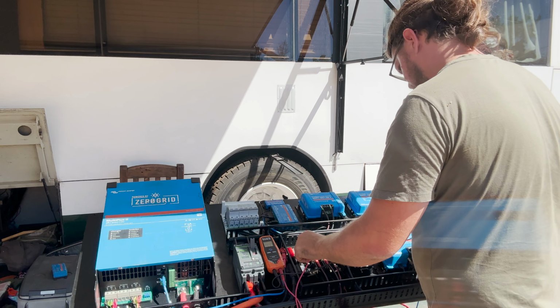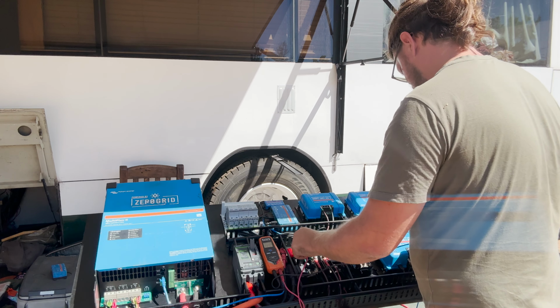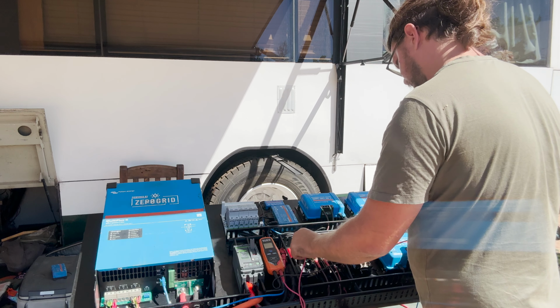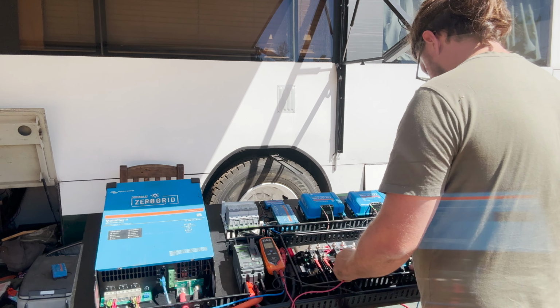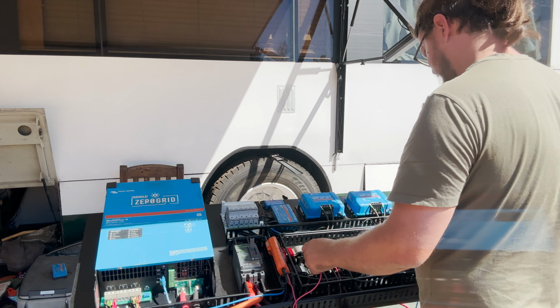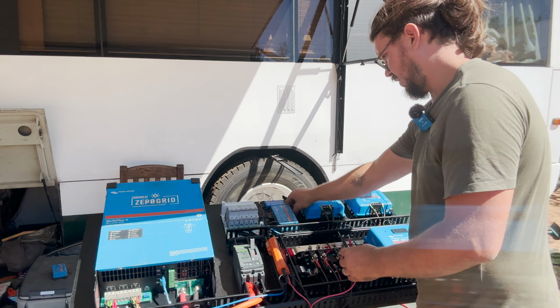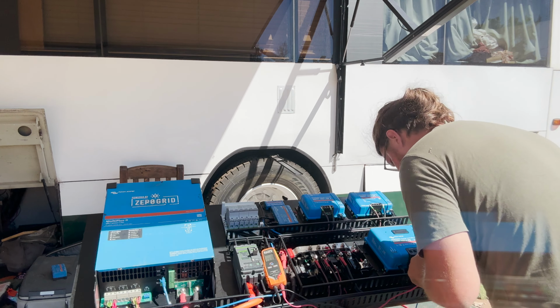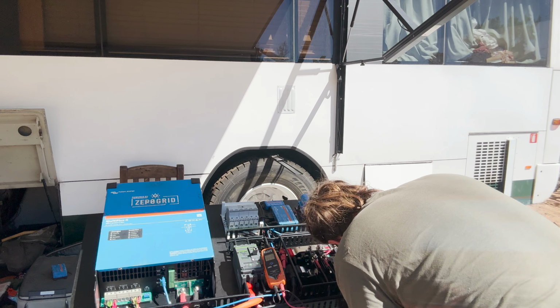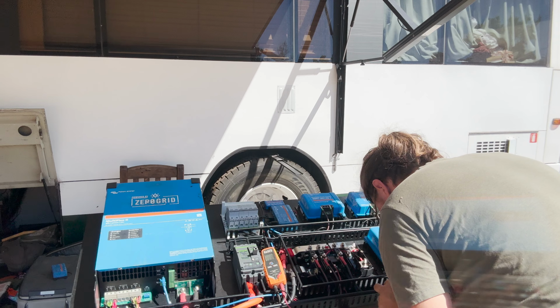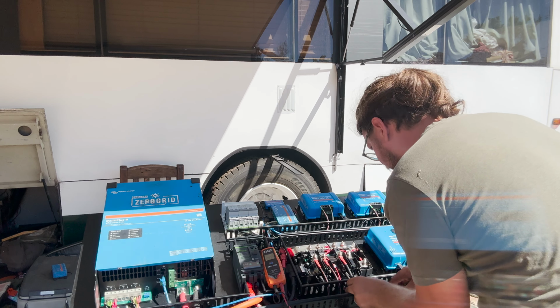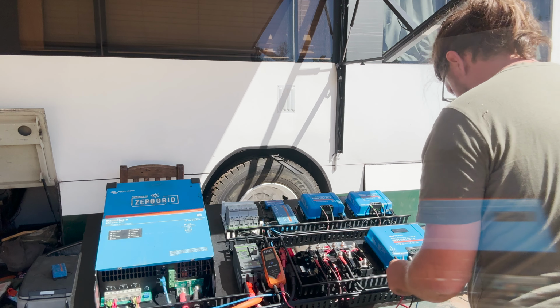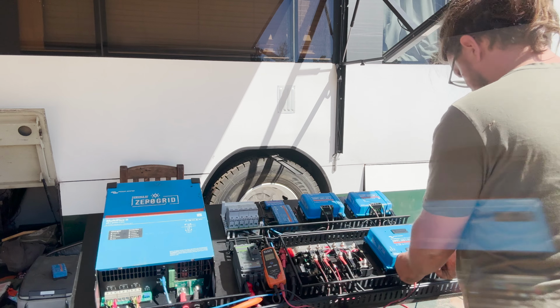So that's the negative, we've got no connection there. Oops, that's that one, they've got the negative there as well. It's a little bit hard because we're picking up resistance through the loads, and that's where a real visual inspection works really well, so we can see where this cable goes. So that's that positive and that's that negative.